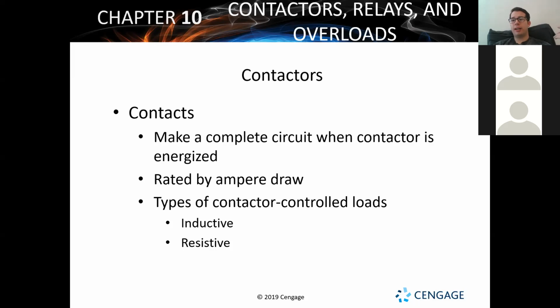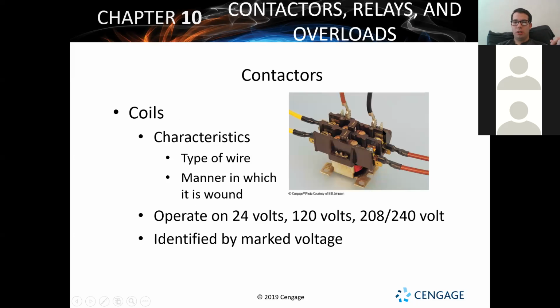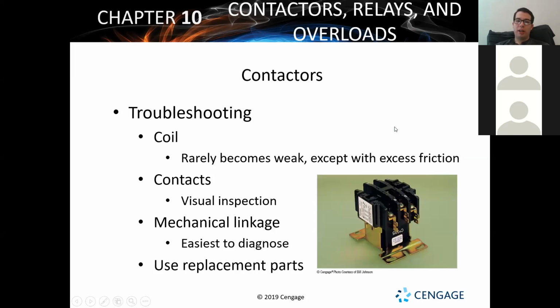But the contactor contacts, these are really where you're going to test your high voltage side of things, where you're going to test that load voltage and make sure the power is actually passing through to your different loads. Is the power even coming in to your system? Besides the high voltage contacts, you've also got your low voltage connections to your coil, and that's usually going to read 24 or 120, depending on what kind of control we've got. Again, a coil rarely becomes weak except from excessive friction.